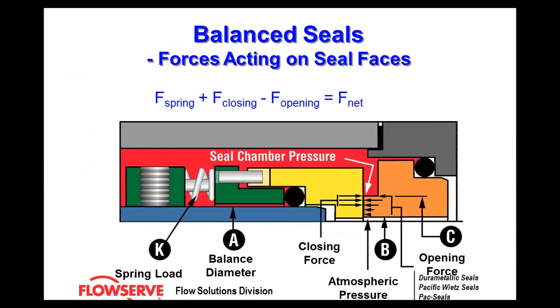Here's the orientation of a balanced seal. Following the spring at point K, you'll notice that the inline force of the spring is above where the actual mechanical seal faces touch. This region in blue, as it interacts with the yellow seal faces, is referred to as the balanced shoulder. So: if you see the springs in line with the face, you have an unbalanced seal; if you see the springs above the face, you have a balanced seal.